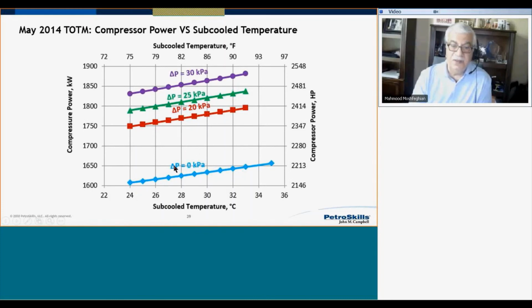If there is no pressure drop in that heat exchanger on the gas side, that works perfectly, but that would be in our dream only. Realistically, we have pressure drop, and the pressure drop causes the power requirement to go up much higher. Again, we have to be careful when you use this kind of arrangement. The only time it may work is when we use an external source for subcooling. If you use an external heat exchanger for subcooling, that works. If I have some cooling gas or some liquid available, I can use it as an external source.